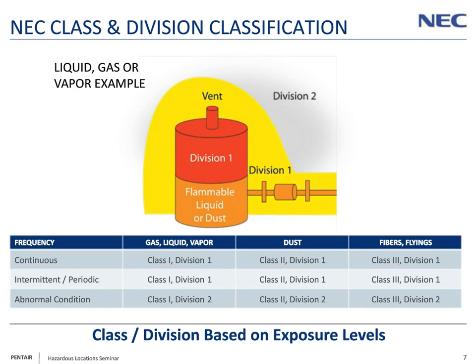Class 1 is for gas, liquids, and vapors. Class 2 is for dust. So think of agricultural applications or coal-fired power plants, for example, would have Class 2 areas. Class 3 is for fibers and flyings, so that's broadly kind of textiles, for example. Class 1 is the most commonly used and deployed, which is oil and gas, petrochemical, chemical plants.